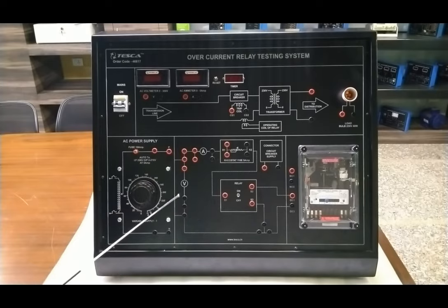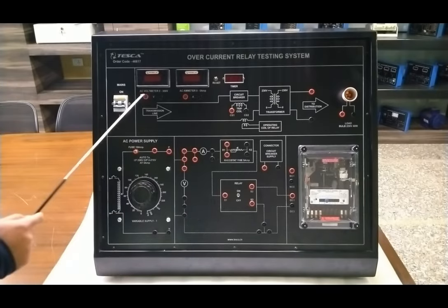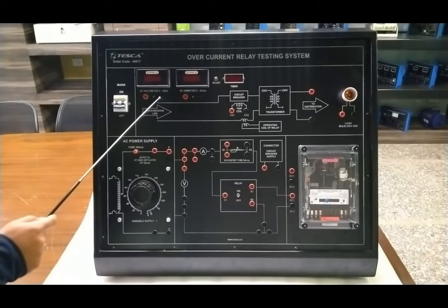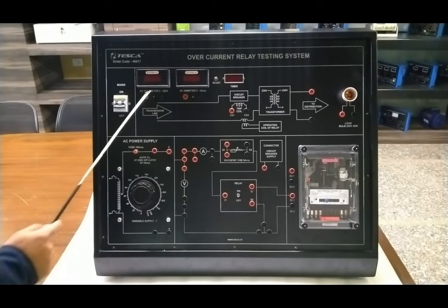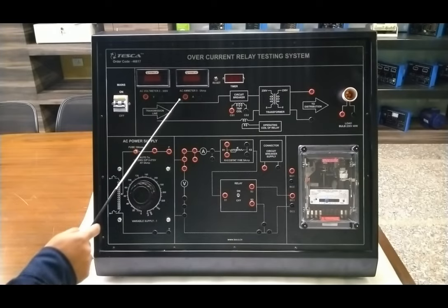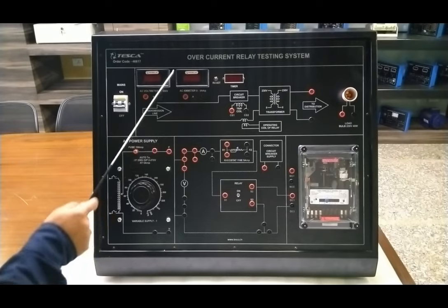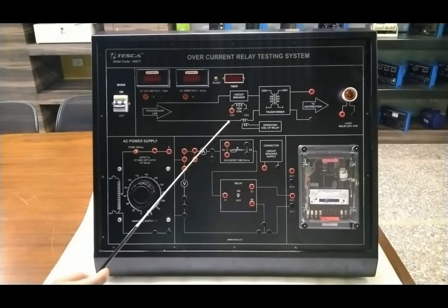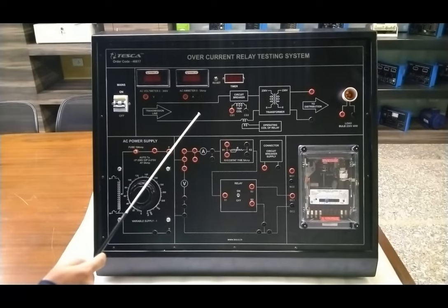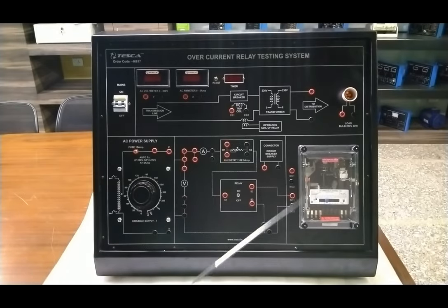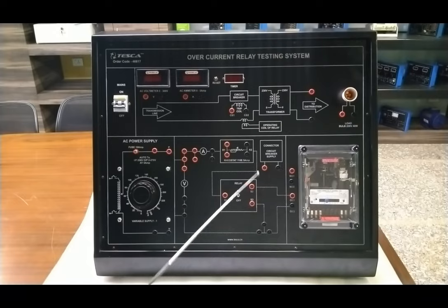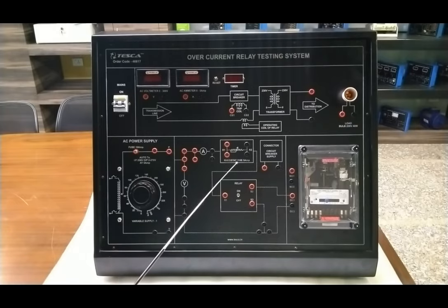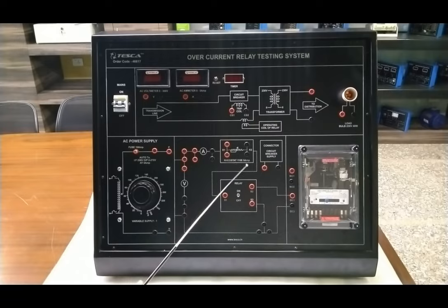We use the voltmeter at this place — this is the AC voltmeter to measure voltage range from 0 to 300 volts. We have a supply of 270 volt maximum so we can easily measure the supply with this AC voltmeter. Then this is the AC ammeter so that we can observe the current passing through the relay coil. The current and time settings described in the overcurrent relay testing system will apply. We will connect a rheostat to adjust the current value — a rheostat of 110 ohm at 5 amp value will be connected.